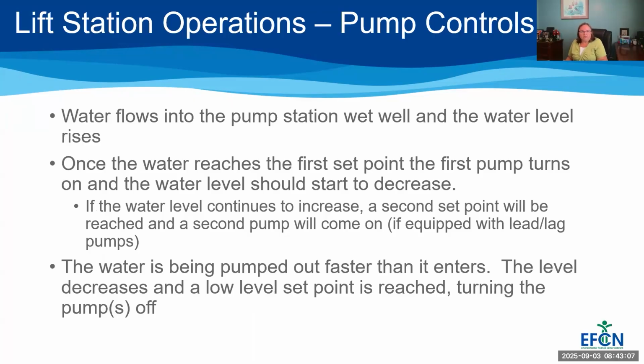The last little thing here to note about your pump controls is that your water is, of course, flowing into the pump station, into the wet well, and the water level is rising, rising, rising. And then once the water reaches that first set point, the first pump will turn on, and the water level should start to decrease. However, sometimes the water level is not decreasing fast enough, or it's continuing to increase. That's where we would have a lead lag pump. If you have lead lag pumps, that's designed for lift stations that may have variable amounts of water coming into them at certain times of day, because maybe there's a manufacturing plant or things that can cause the flow to vary throughout the day. And so sometimes you would have to turn the second pump on to cause the level to decrease.